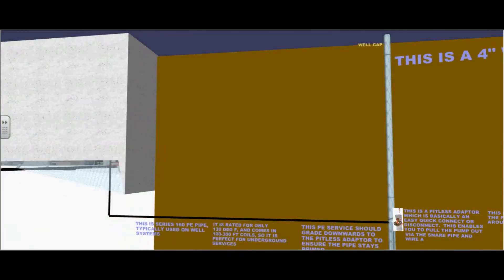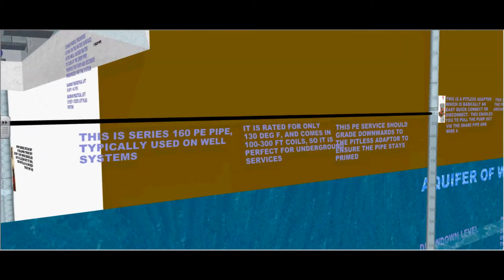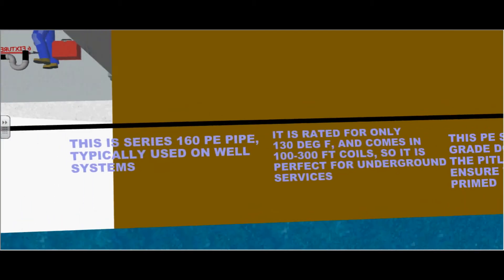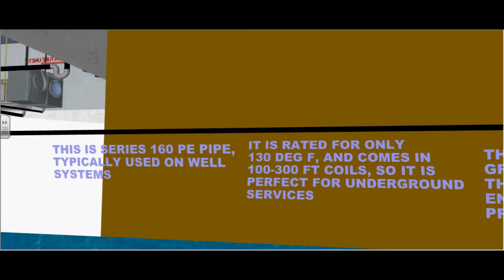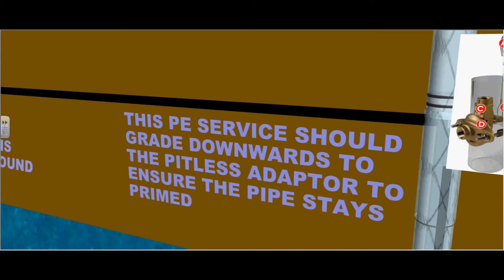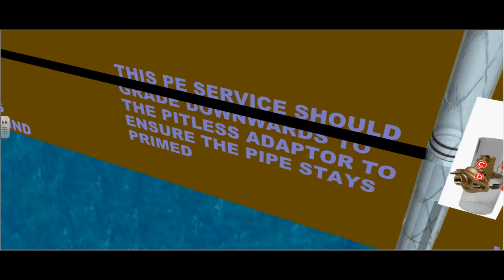This is a series 160 polyethylene pipe typically used on well systems. It is rated for only 130 degrees Fahrenheit and comes in 100 to 300 foot coils so it is perfect for underground services. This polyethylene service should grade downwards towards the pitless adapter to ensure that the pipe stays primed.